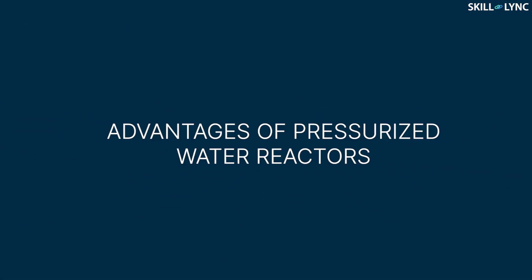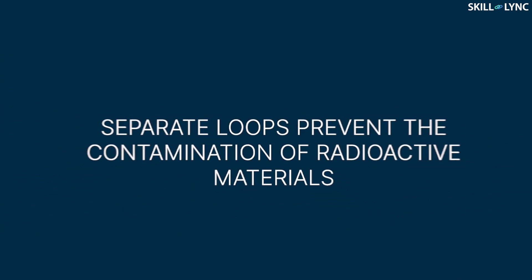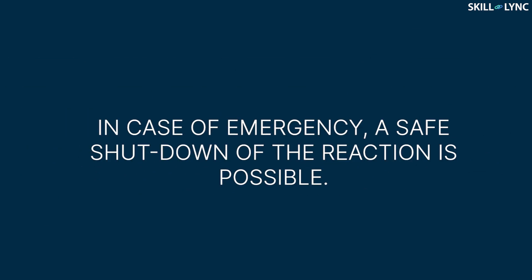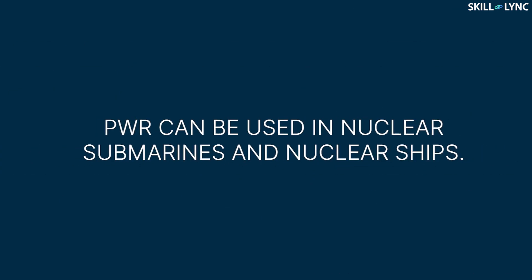Now, let's see some advantages of the most common nuclear reactor. First, pressurized water reactors are very stable due to the self-regulating process. Due to the primary and secondary loops being separate, the secondary loop does not get contaminated by radioactive materials. In case of loss of power, the control rods held by electromagnets fall into the core by gravity, which shuts down the reaction safely. Also, pressurized water reactors, due to their compactness, can be used in nuclear submarines and nuclear ships.